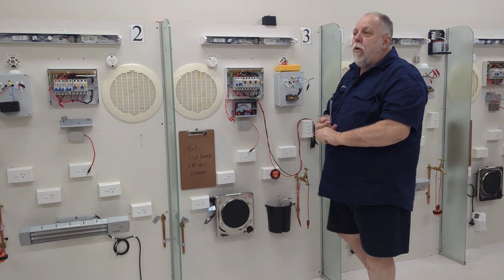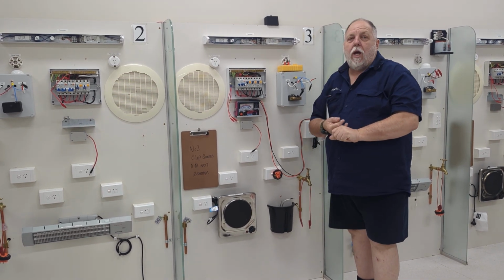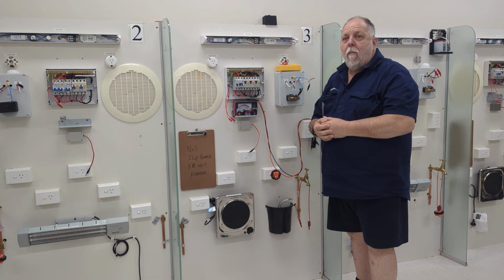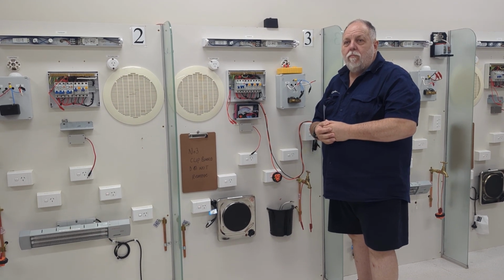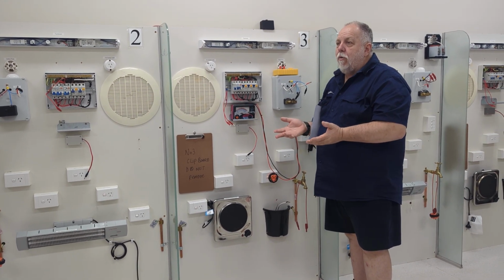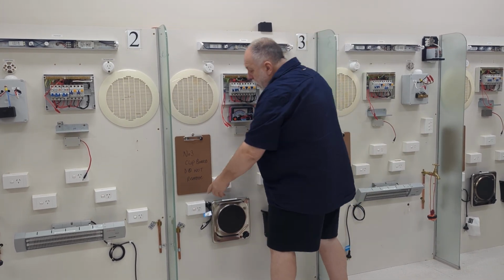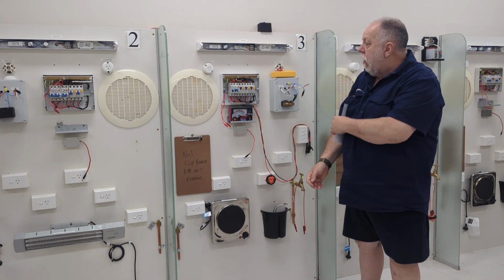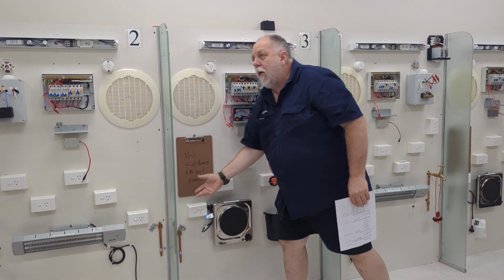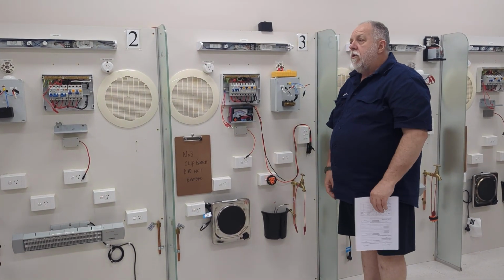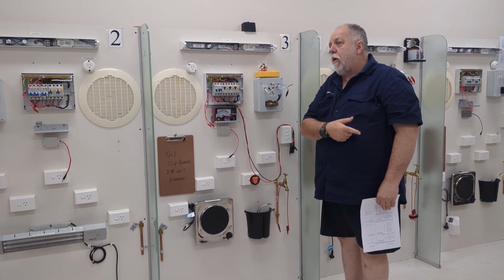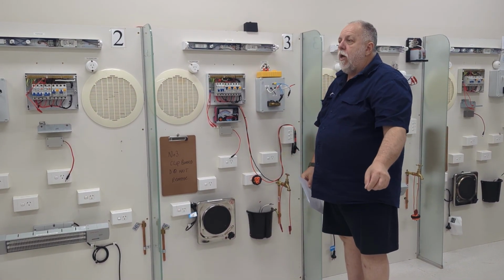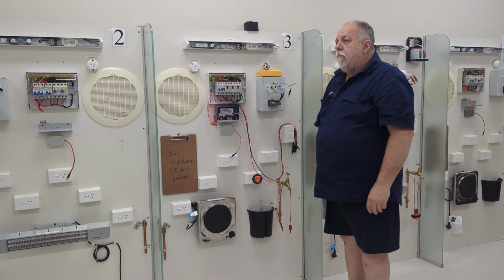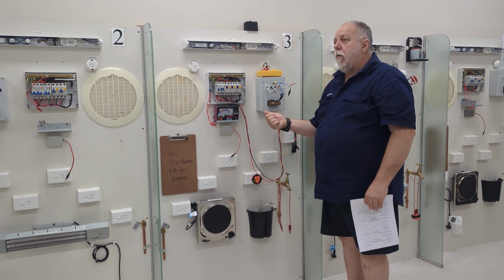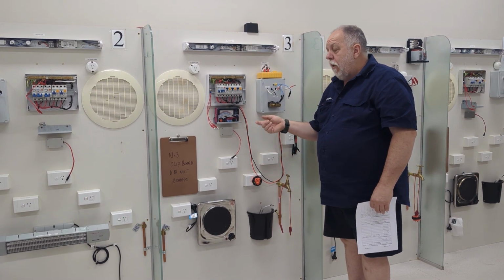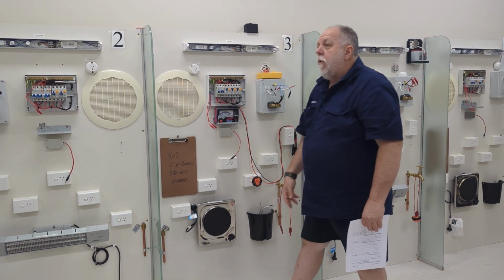Another type of earth we've got is the strip earth, okay? If we have a strip earth, how do we do a test then? You can't do a test on a strip earth, all right? The problem is because it's in the ground, there's no connection point. What we're doing here, from here to this earth electrode, is just making sure we don't have a high resistance, all right? A strip earth is very hard to test because it's buried directly in the ground, unless you've got some point where it's open and you can do a continuity test. There's no connection point, there's no tag to be put on a strip earth, but we have to have a tag like this down here that we don't remove.